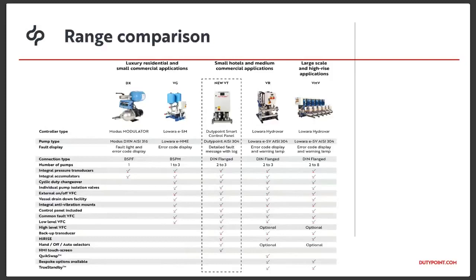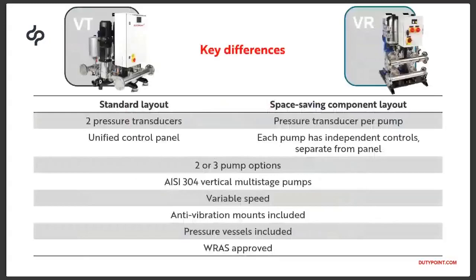But here is a key comparison between the standard, the VT and the VR. So starting at the top, the VT is this more standard layout with the suction and discharge manifolds opposite each other. Two pressure transducers. We always recommend having at least one backup transducer because that is the key sensor of the unit. Whereas the VR has a pressure transducer per pump. So if there's 3 pumps, that means there are 3 pressure transducers, which is great for backup and redundancy, but it's not always necessary to have that level of redundancy.